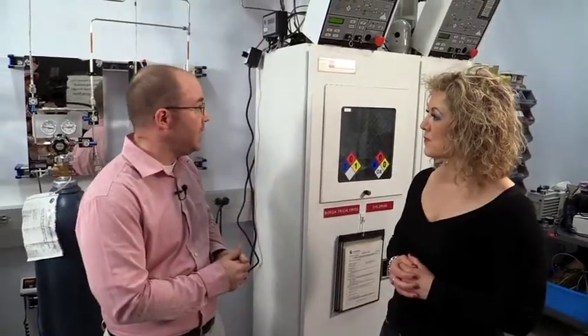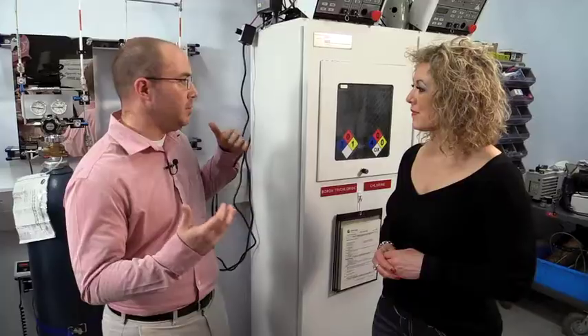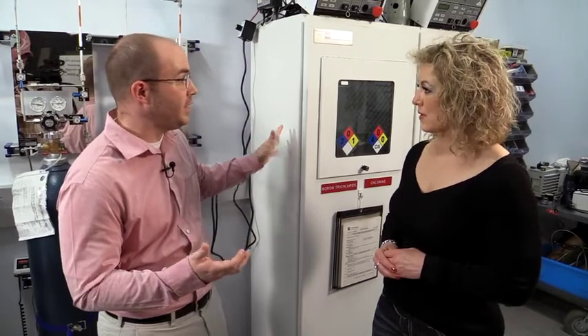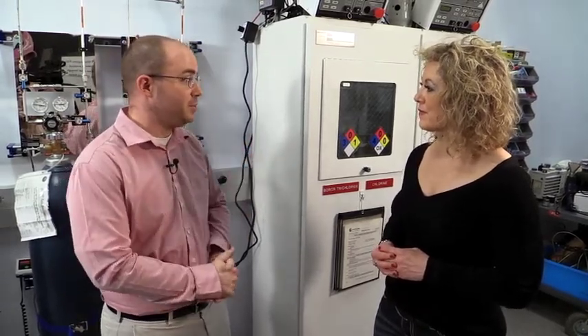So the sensors are part of a pretty sophisticated monitoring system. We have several gases throughout our lab — maybe about 12 different gas cabinets for different toxic gases. Each of those is hooked up to a central alarm system that will trigger a hazmat alarm if any one of them detects a certain threshold of parts per million of that gas. This one is specifically tuned to chlorine, as opposed to others which might be tuned to different gases. If anything happens, it'll trigger that large alarm and everybody will know to evacuate the building at first opportunity.